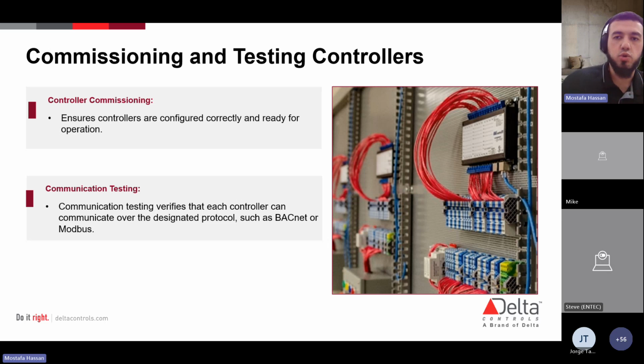Commissioning is going to ensure that controllers are configured correctly and ready for operation. Right. So you're going to look at each controller. You're going to verify the initial settings, load control programs. And this can actually be done in a simulated condition as well. Actually, I think there's a mention of that soon. So you're going to conduct functionality checks, you're going to confirm each controller's readiness, and you're going to ensure that the building automation system can perform as designed.